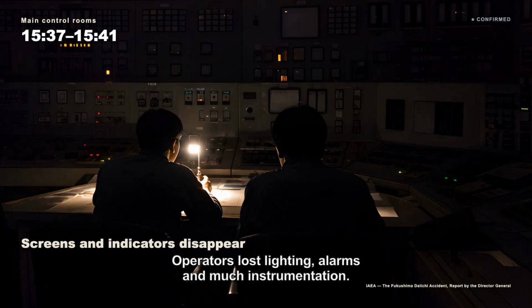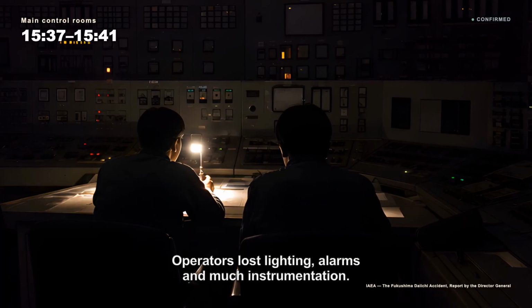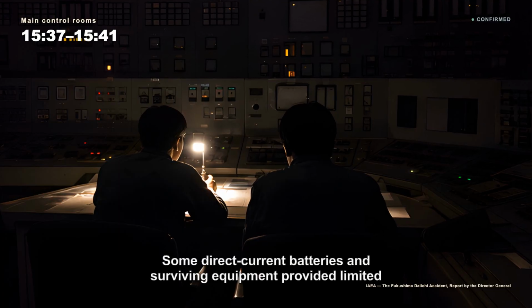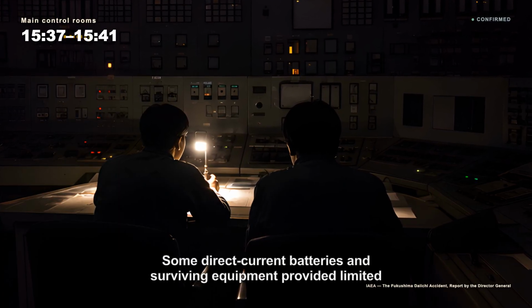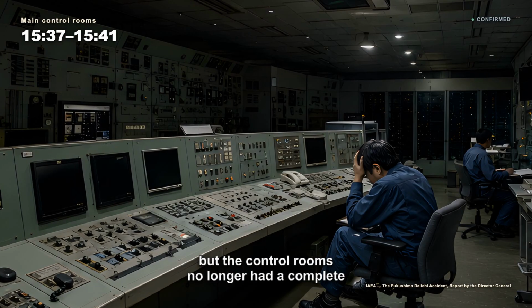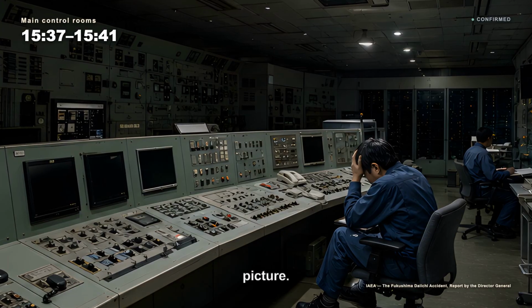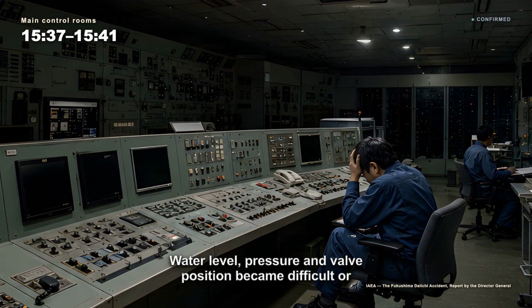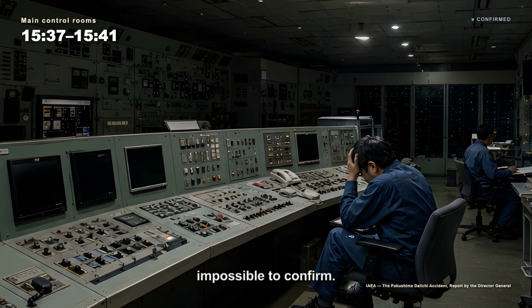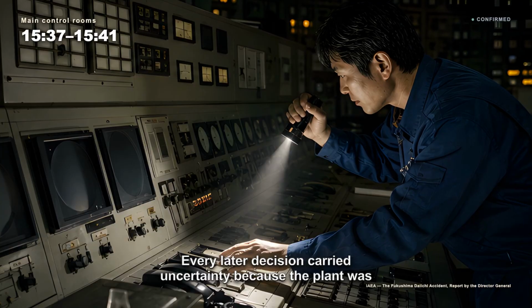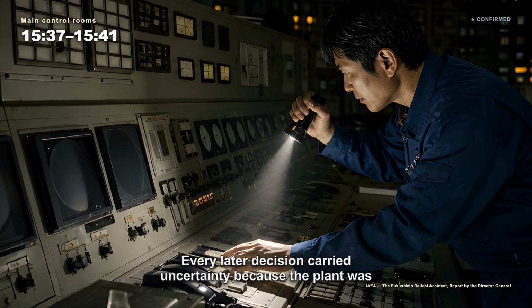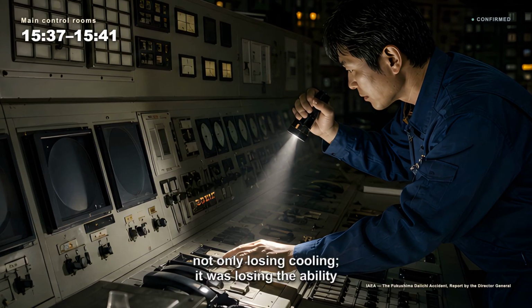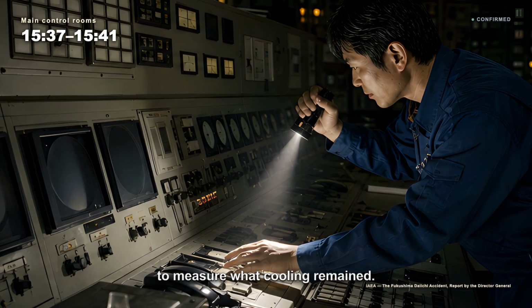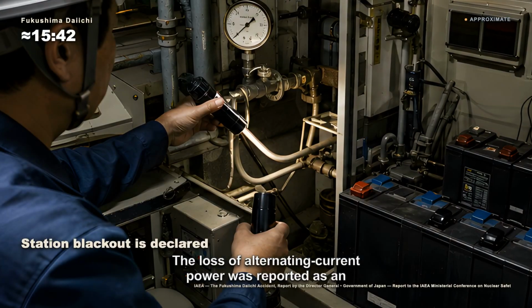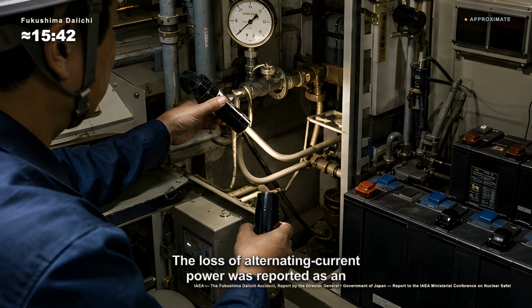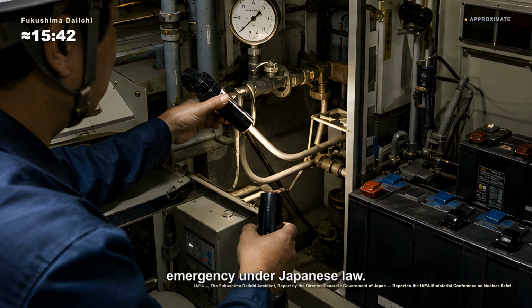Operators lost lighting, alarms, and much instrumentation. Some direct current batteries and surviving equipment provided limited capability, but the control rooms no longer had a complete picture. Water level, pressure, and valve position became difficult or impossible to confirm. Every later decision carried uncertainty because the plant was not only losing cooling, it was losing the ability to measure what cooling remained. The loss of alternating current power was reported as an emergency under Japanese law.